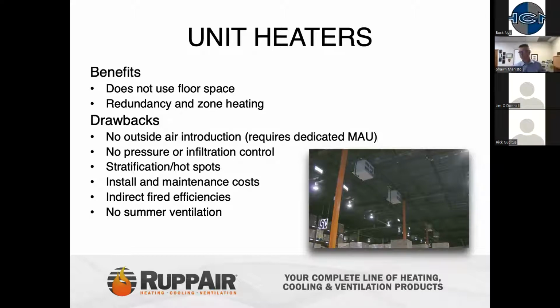The biggest drawback is no outside air introduction. So typically, like I'm actually based in Minnesota here, Minnesota does a lot of unit heaters for some of their speculative type buildings, but they're always going to be accompanied by a makeup air system that's going to be utilized to bring fresh air into the space. So in Minnesota, we're starting to convert a lot more units over to just straight up recirculating style direct fired makeup air systems. No pressure control or infiltration control, can create stratification and hot spots because they're designed just to be the heat source. The indirect fired inefficiencies and really no summer ventilation. So this is kind of just a heat only winter application product.